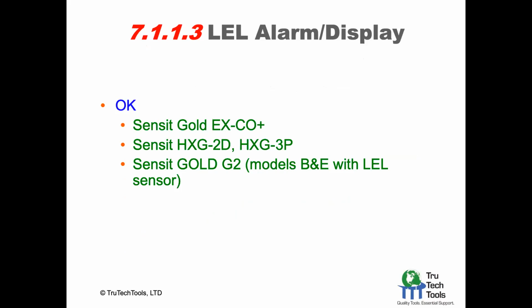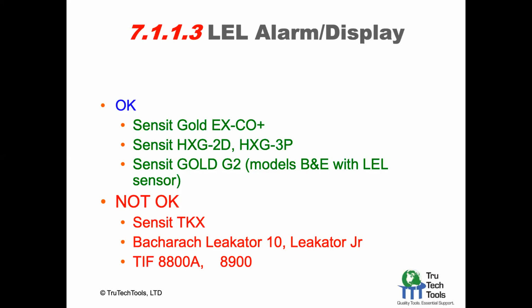Products with an LEL alarm or display, these 3 were the only ones out of the remaining ones that came up with that had an LEL alarm or display. So the Sensit TKX, the Bacharach does not have an LEL display. The TIFs do not have LEL alarms or displays. If they had either one of those, they'd probably still be in the running and still be on the island.